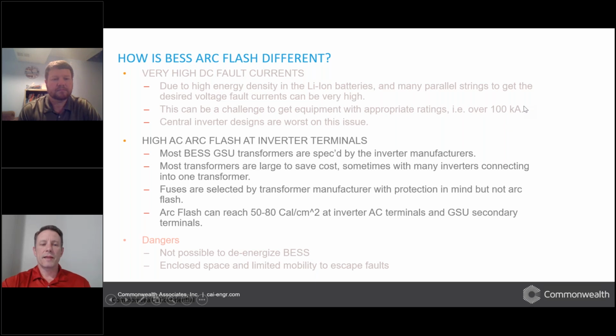For the AC side, the highest arc flash is usually at the transformer low side and the inverter terminals. Quite often these come on a skid together, and you can't really separate them. Usually you won't work on that location, but if you ever have to, the arc flash is going to be extreme. They usually specify the protection for these transformers, the fuses, to save the transformer, not to save the people. So sometimes there's not much we can do about that.